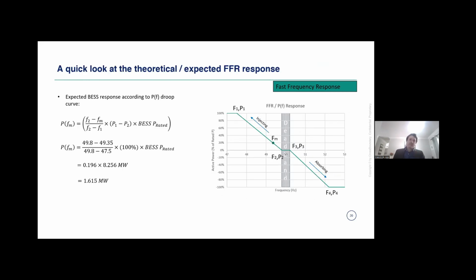Just looking at the theoretical or the expected fast frequency response here, if I use my cursor here, at the point FM, which is essentially where the frequency dipped to, we can see we're in the injection range of our fast frequency response. If we apply the mathematical formula for the amount of active power that we were expecting at this point along our droop curve, we calculated about 1.615 megawatt that was required to be injected by the battery system at a dip of 49.35 hertz.